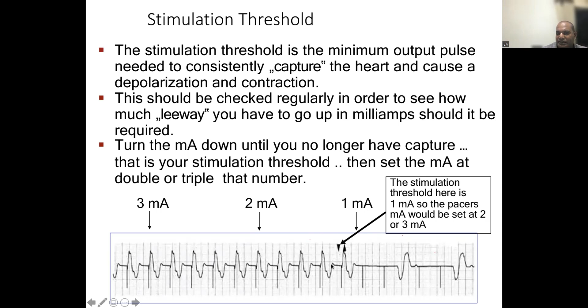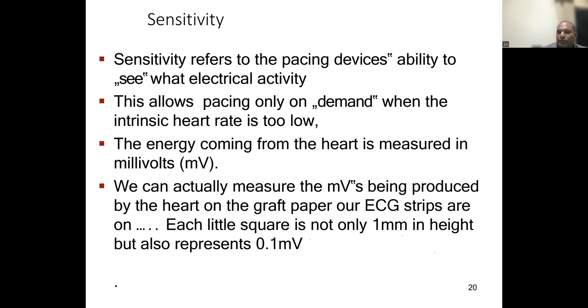And sensing, as I mentioned, is the generator's capability of seeing what's happening there. The pacemaker needs to be able to see what's happening and then decide whether to not do anything or to deliver current output. So this diagram tells you what exactly sensitivity means. Sensing is the capability. Sensitivity is a level that we decide for the pacemaker.